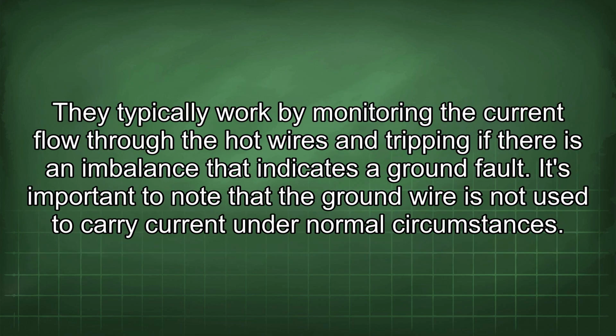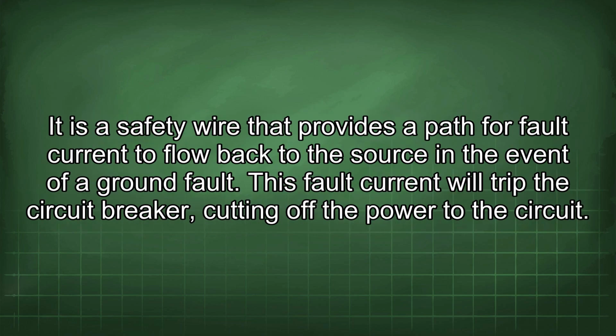They typically work by monitoring the current flow through the hot wires and tripping if there is an imbalance that indicates a ground fault. It's important to note that the ground wire is not used to carry current under normal circumstances. It is a safety wire that provides a path for fault current to flow back to the source in the event of a ground fault. This fault current will trip the circuit breaker, cutting off the power to the circuit.